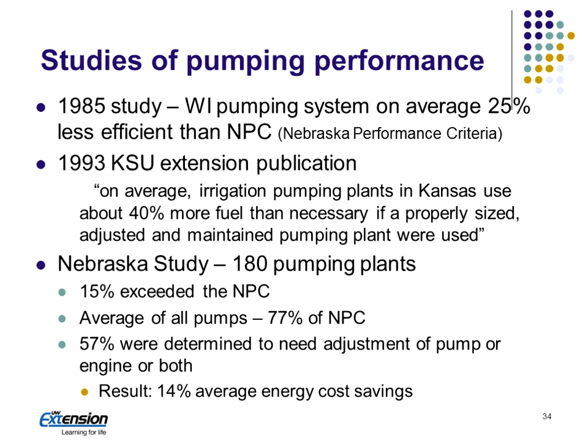So on pump testing, there have been a number of studies throughout the years. Every time they test, they find that our pumps aren't as efficient as they should be. Nebraska does lots of irrigation. They came up with pumping performance criteria. And every time we do one of these tests, we find that here we had an average of 25% less than the criteria in Wisconsin in '85.